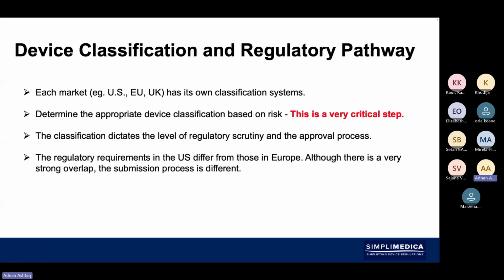So when we look at device classification in the regulatory pathway, each market has got its own classification systems, and we will look at that in the coming slides. We have to determine the appropriate device classification, which is based on risk. That's very, very critical, and which we'll have a look at. The classification dictates the level of regulatory scrutiny and the approval process. The regulatory requirements in the US differ from those in Europe, although there's a very strong overlap and the submission process is different.